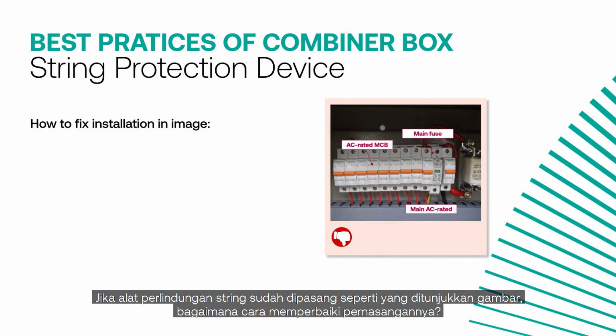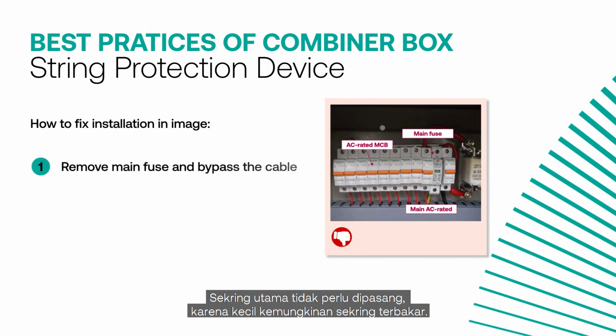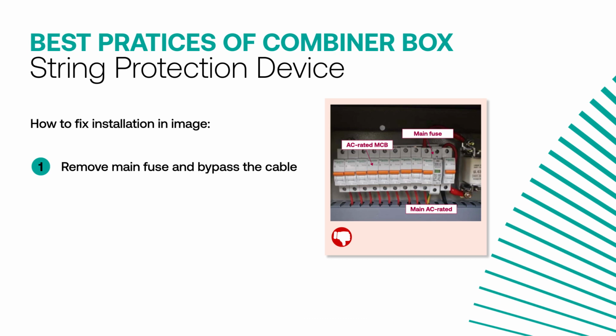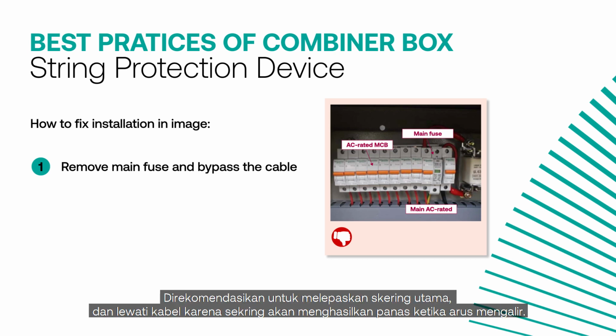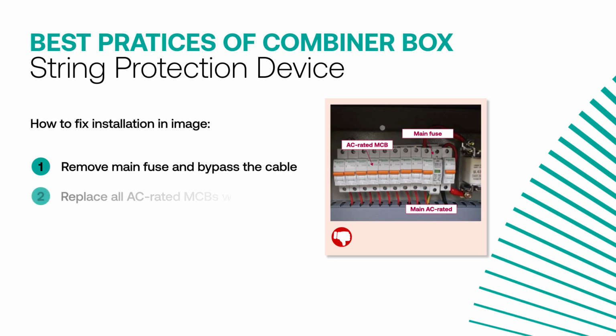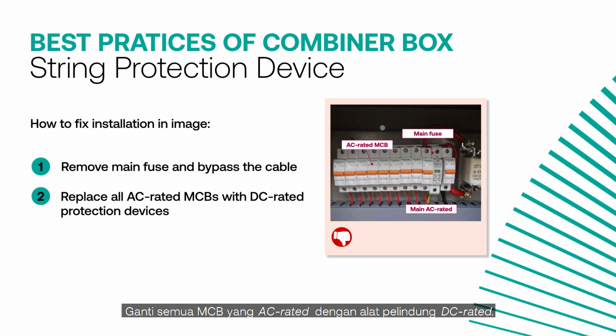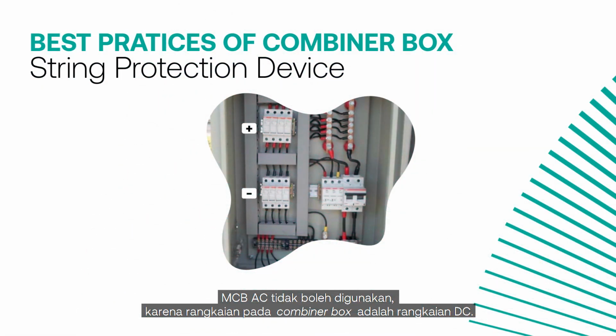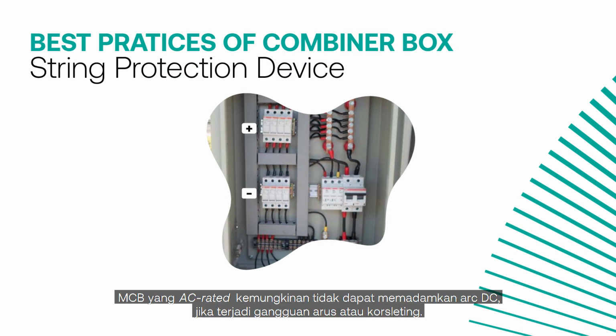If string protection devices have been installed as shown in the picture, how to fix such an installation? The main fuse is not necessary as there is only a small chance the fuse will burn. It is recommended to remove the main fuse and bypass the cable, since the fuse will generate heat when current is flowing. Replace all AC-rated MCBs with DC-rated protection devices. AC MCBs must not be used because the circuit in the combiner box is a DC circuit. An AC-rated MCB may not be able to extinguish the DC arc in case of fault current or short circuit current.